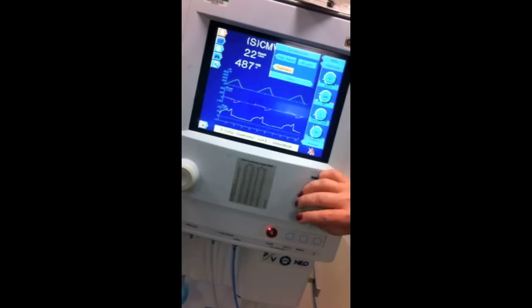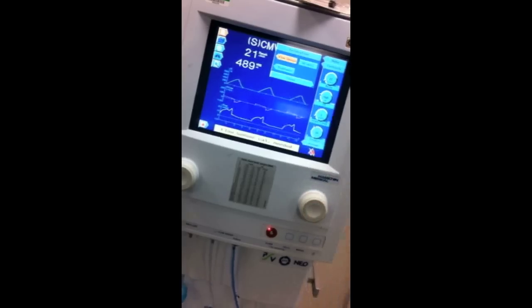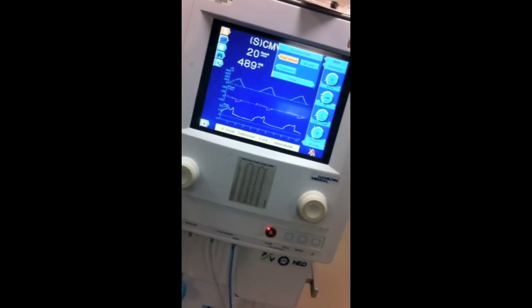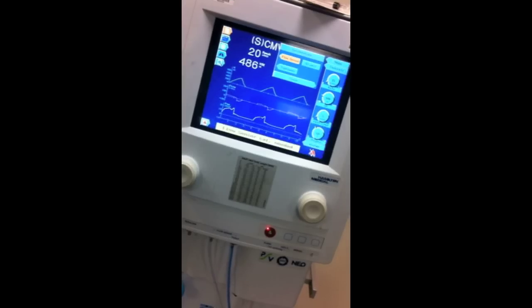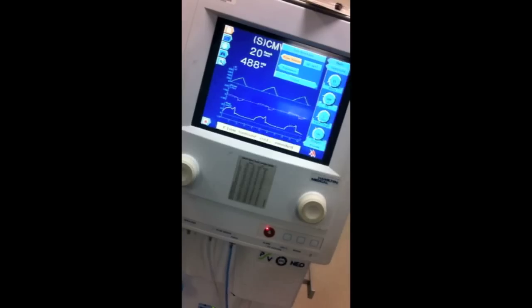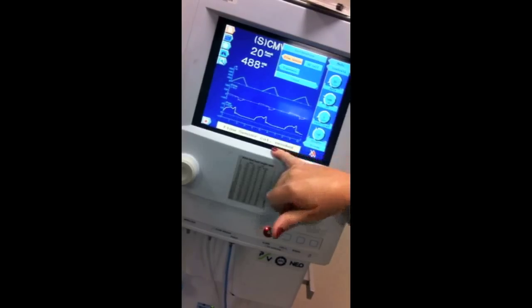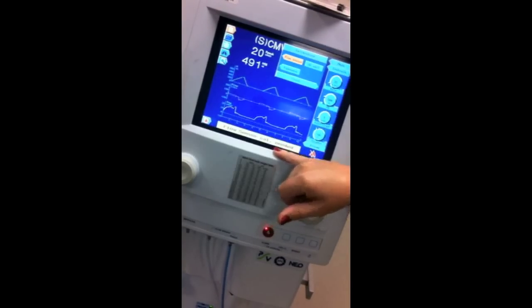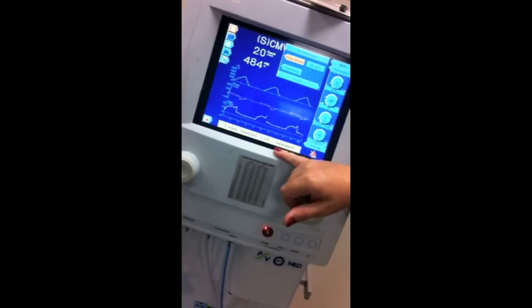So first thing we're going to do is the flow sensor, and it's checking this to make sure that it works and that it calibrates for how much flow. You're going to see when we do this that it puts a whole bunch of flow through there, and you can see the sensor going like that to test it. It's also telling us it wants us to do a flow sensor cal. Sometimes it will do that just while you're ventilating, and you'll need to stop and calibrate your flow sensor.